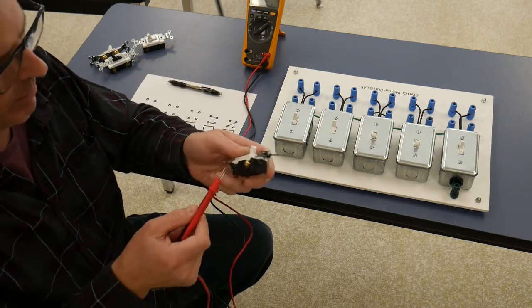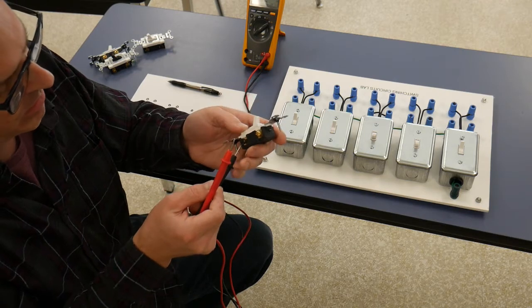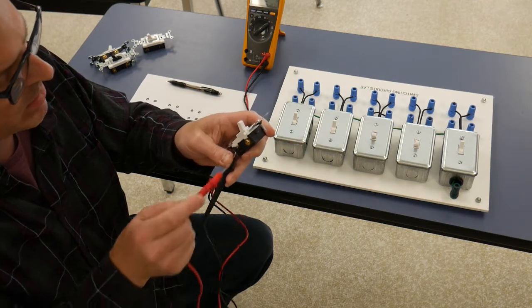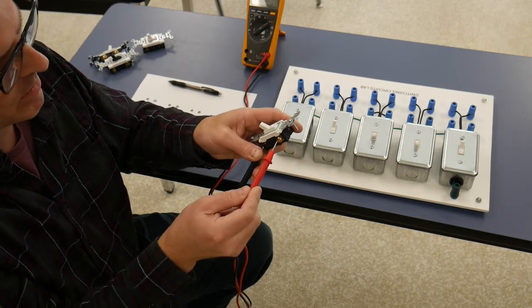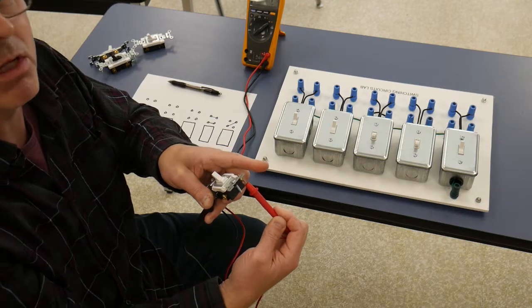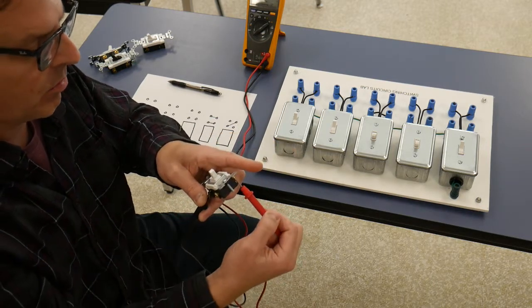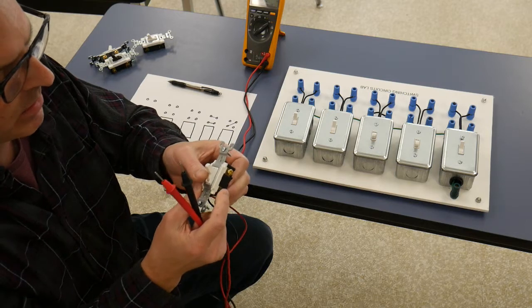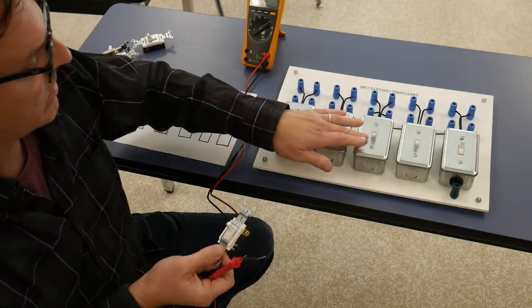So the three-way, if I'm looking at it in one position with the switch there, the black screw is my common. That's my pivot point. This guy here, we get a beep. If I turn the switch to the opposite position, I don't get a beep. But if I go to the other terminal, I will now get a beep. Okay? Flip it back. No beep there. Beep on this side. Okay? So the black is my pivot point. So we're trying to isolate the common pivot point and then the two traveler terminals in this next switch.